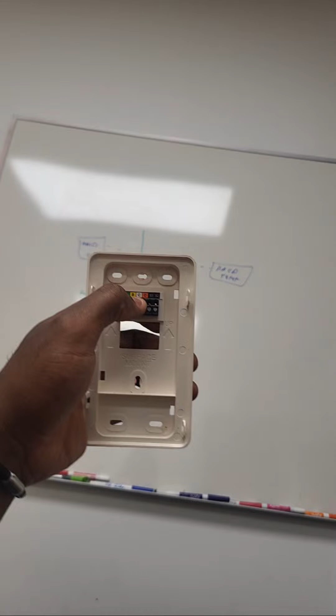But guys, when I went downstairs to the furnace, I did have 24 volts, right? I had 24 volts from C to D, and the customer had the switch off, so I turned the switch back on. And guys, in my scenario, I actually did have 24 volts between C and D. And for you guys just coming in here, once again, this is just a no AC call on the Carrier communicating setup. This customer had a 90% furnace inside, and she had a straight AC unit outside. But guys, this was a simple diagnosis. I got there, and to resume what I was just saying, the thermostat was blank. All I did was check for 24 volts between C and D, and I had 24 volts.